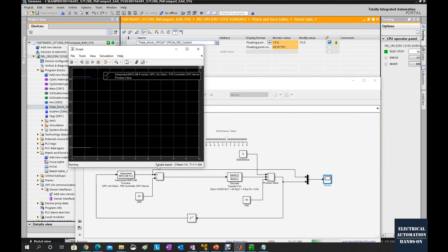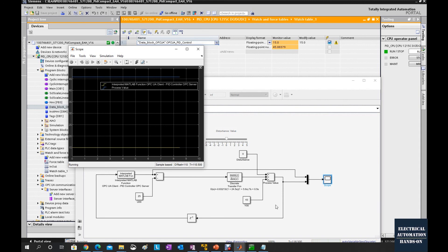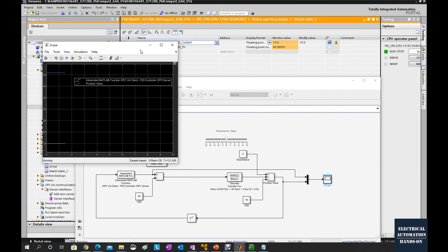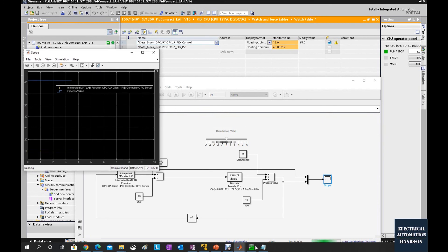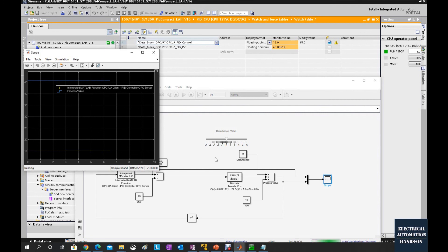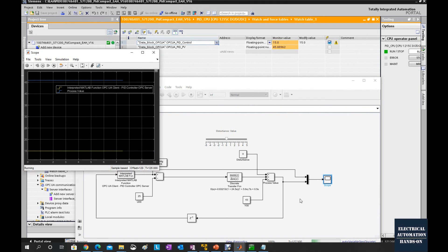This also means the loop signal in MATLAB Simulink is working. Because from the PID control signal we provide 15, and then the process model feedback returns 45.8 — so the whole loop is working now. We have successfully set up the OPC UA client function inside MATLAB and used MATLAB Simulink to call this sub-program, allowing MATLAB to communicate with the OPC UA server on the PLC. The entire MATLAB Simulink control loop is operational.